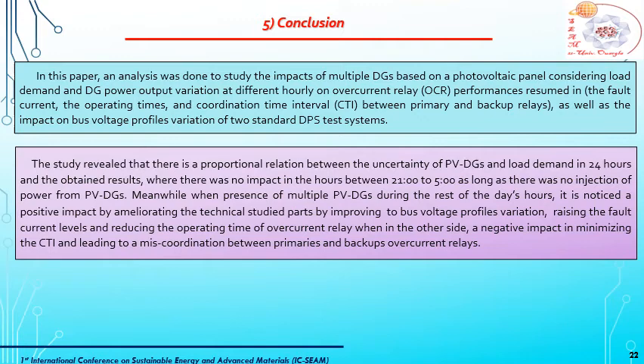Meanwhile, with the presence of multiple PVDG during the rest of the day's hours, a positive impact is noticed by ameliorating the technical studied parts: improving the bus voltage profile variation, raising the fault current levels, and reducing the operating time of overcurrent relays. On the other side, there is a negative impact in minimizing the coordination time interval and leading to miscoordination between primary and backup overcurrent relays.